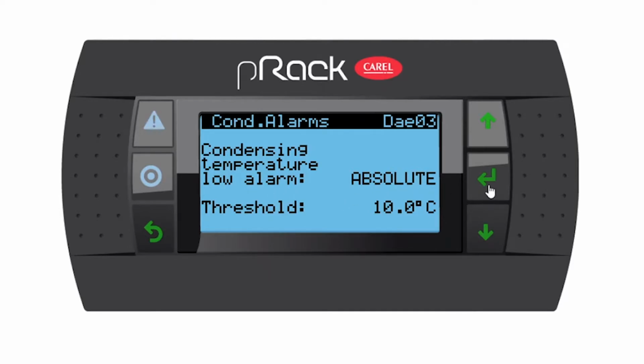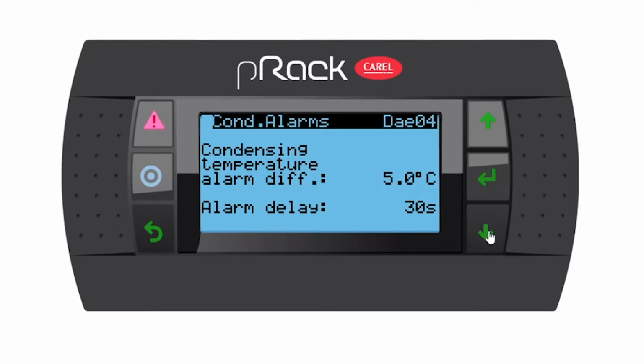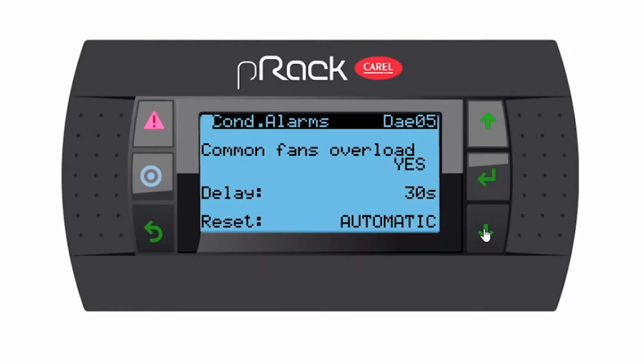Condensing temperature low alarm, absolute. I'm going to leave it on absolute, but I'm going to change my threshold up to, I'm going to start at 20 degrees Celsius. And remember, if you set this too high, you may have some nuisance alarms. So just set it a little bit lower, or go and have a look why you're not condensing at the correct temperature. 20, perfect. Let's go down. Condensing temperature alarm differential of 5 and delay of 30 seconds. That's perfect. I'm going to go down.